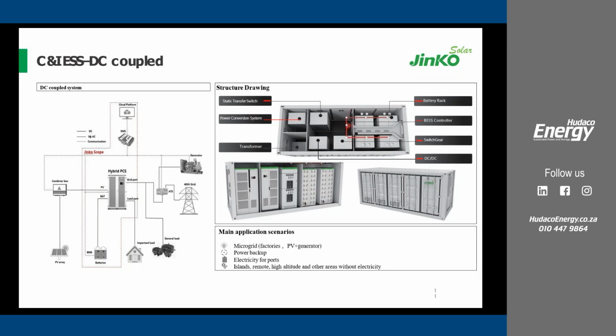So without the cooling system, and assuming the temperature goes to, let's say, 45 or 50 degrees inside the compartment where you're having the batteries, then ideally the performance would drop, sometimes even going below 2000 cycles, which ideally makes the battery last not more than 5 or not more than 10 years as expected. So ideally the cooling system is mandatory, and that we recommend.